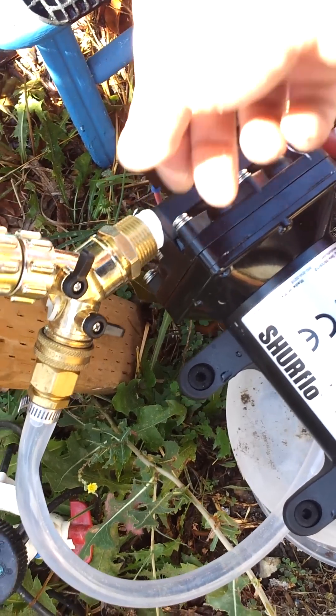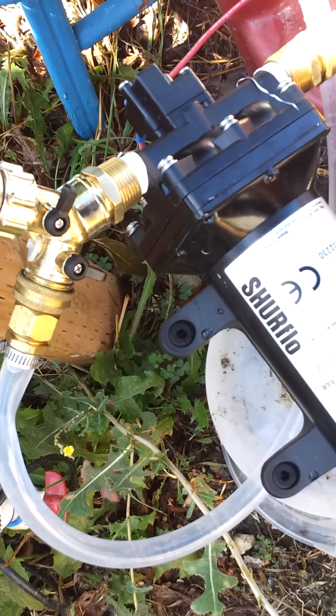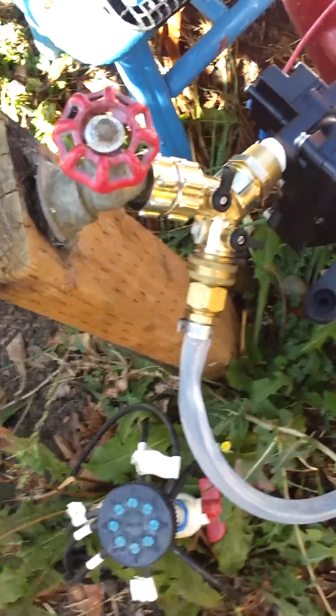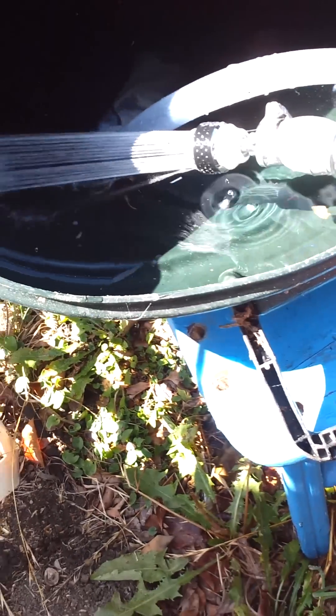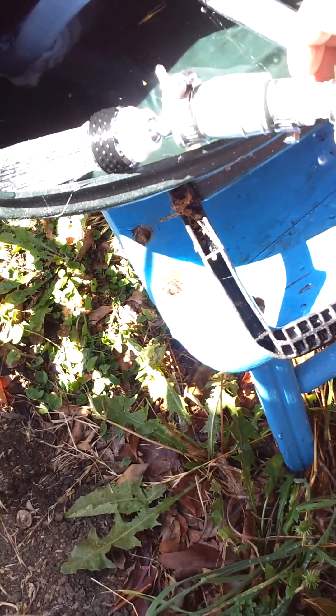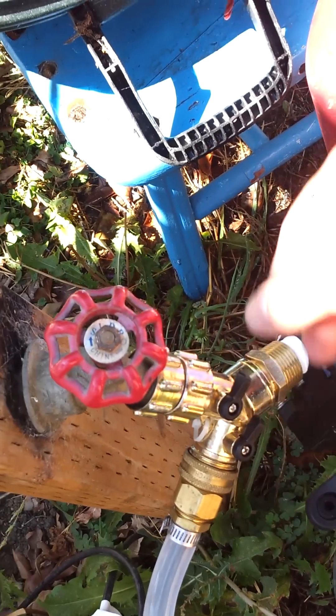This pump is 4 gallons per minute at 55 PSI. The front of the house has the bathroom sink on, the middle has the kitchen sink on, and toward the back the bathroom sink and shower are both on. I'm going to show you the shower. Opening it all the way — that's the water pressure for the whole house. Not bad. I'll turn the house off now.